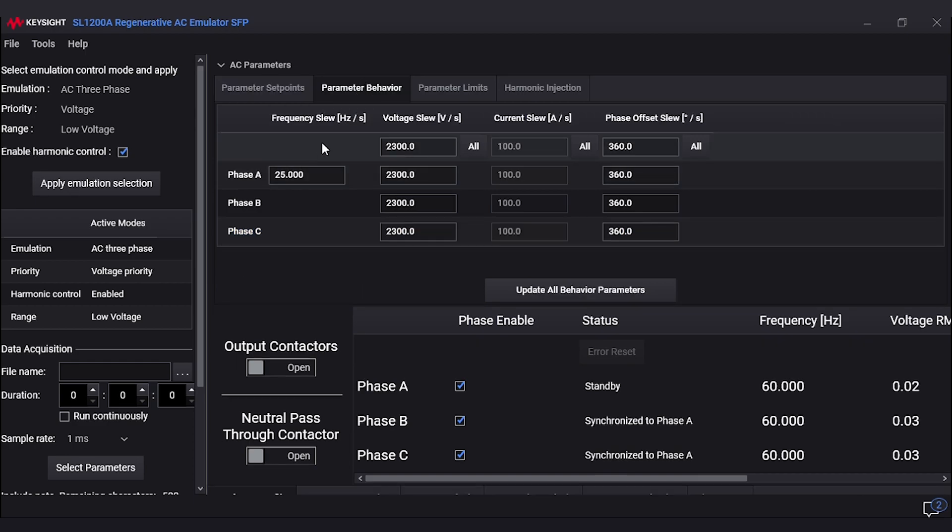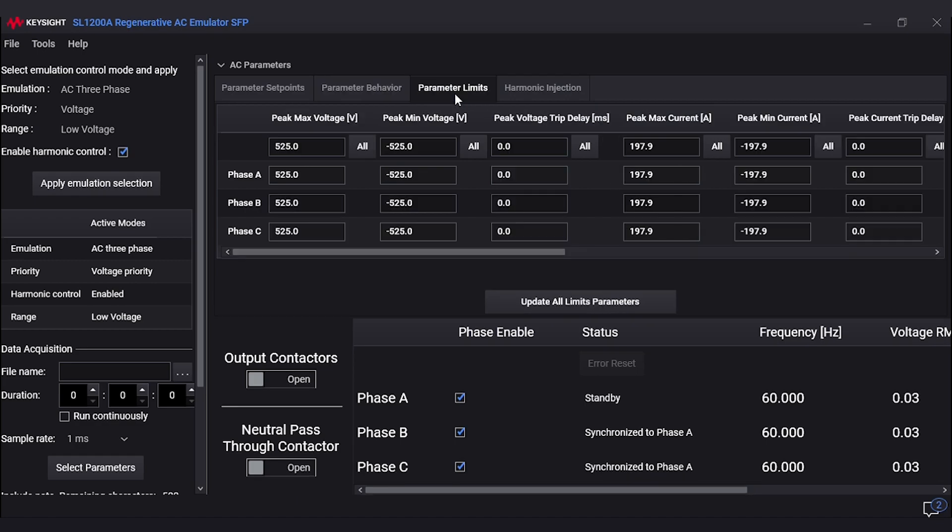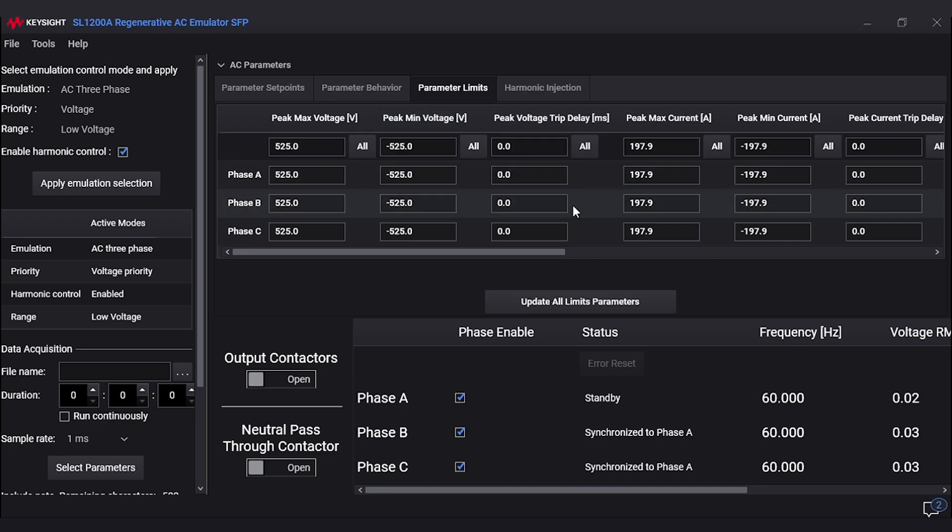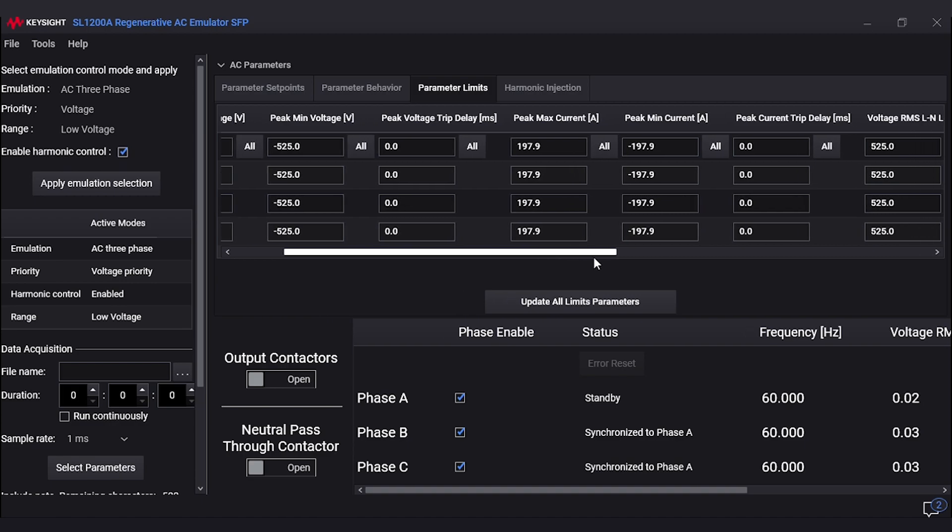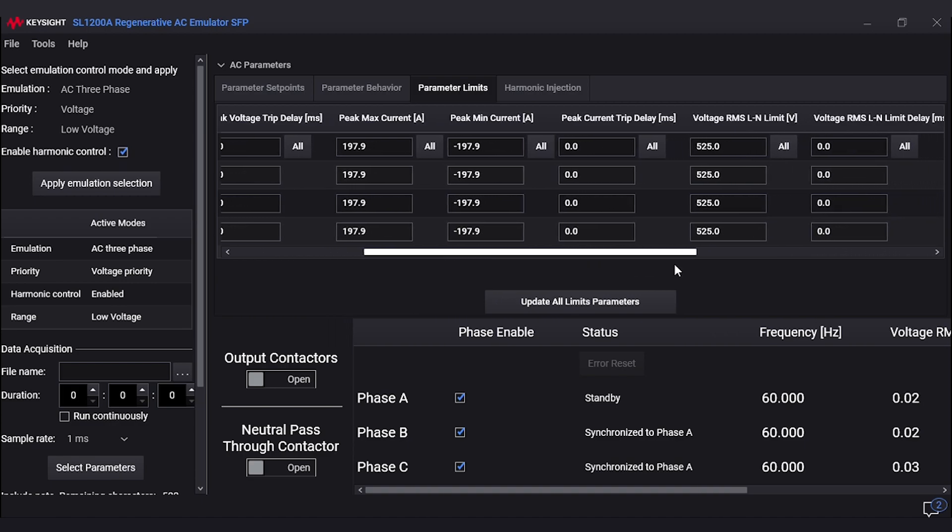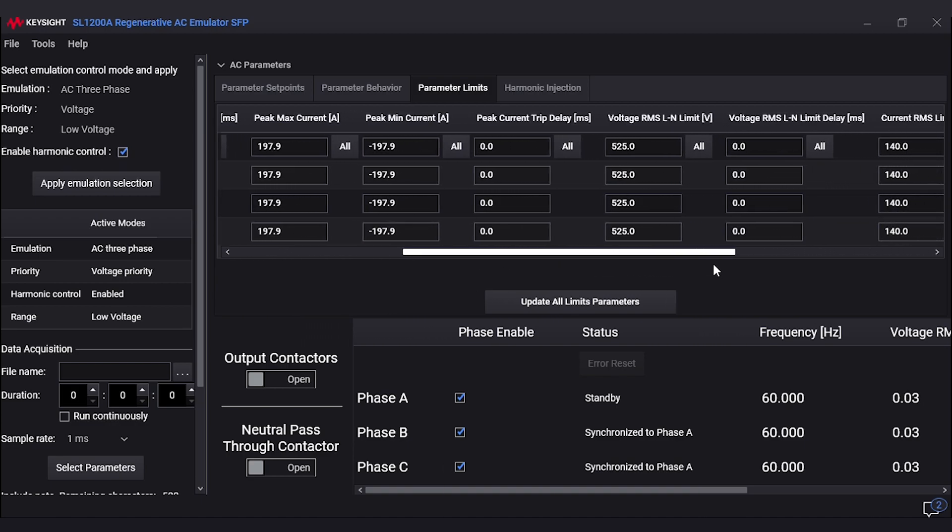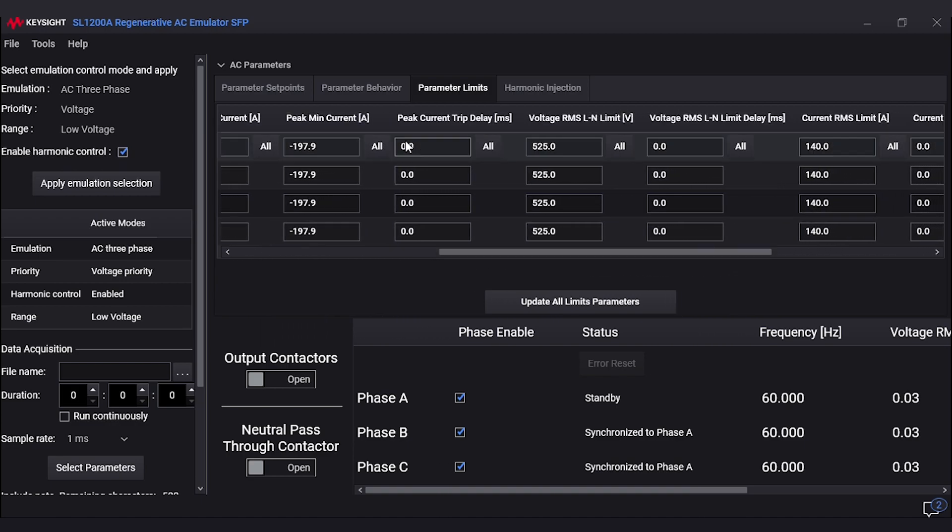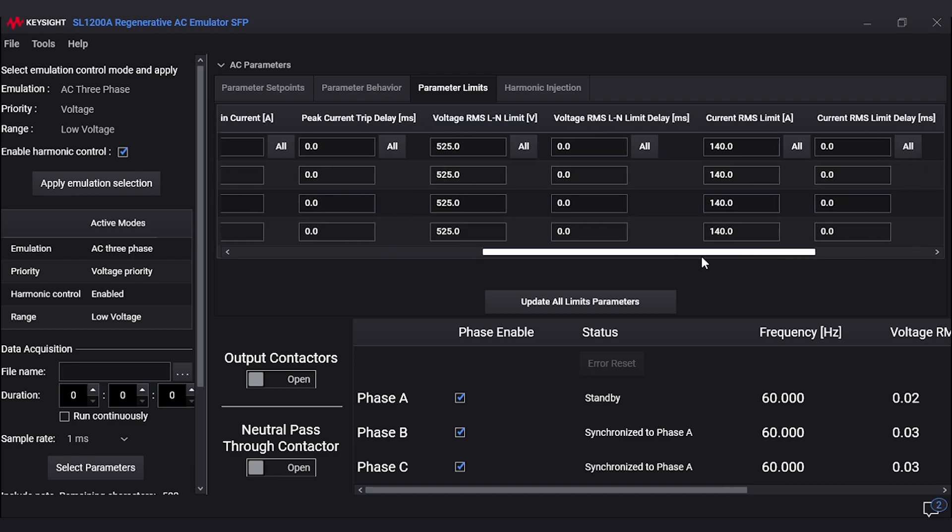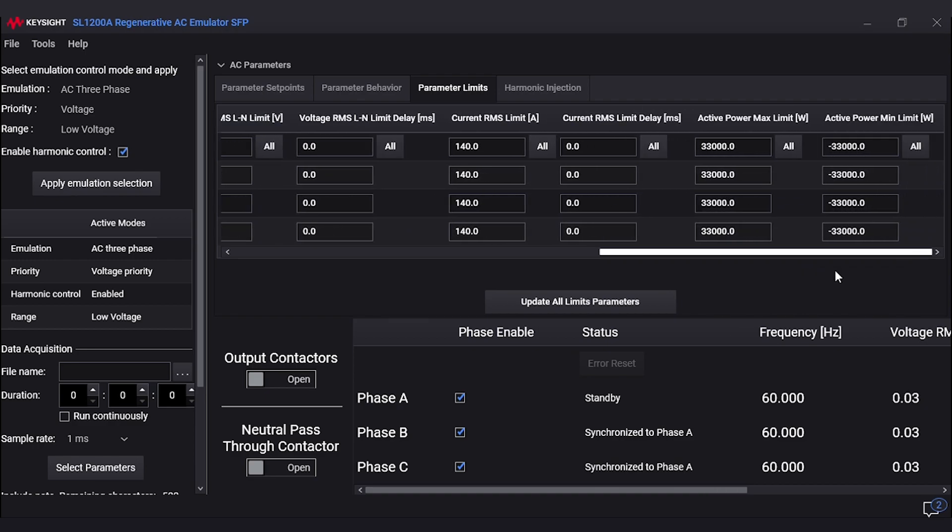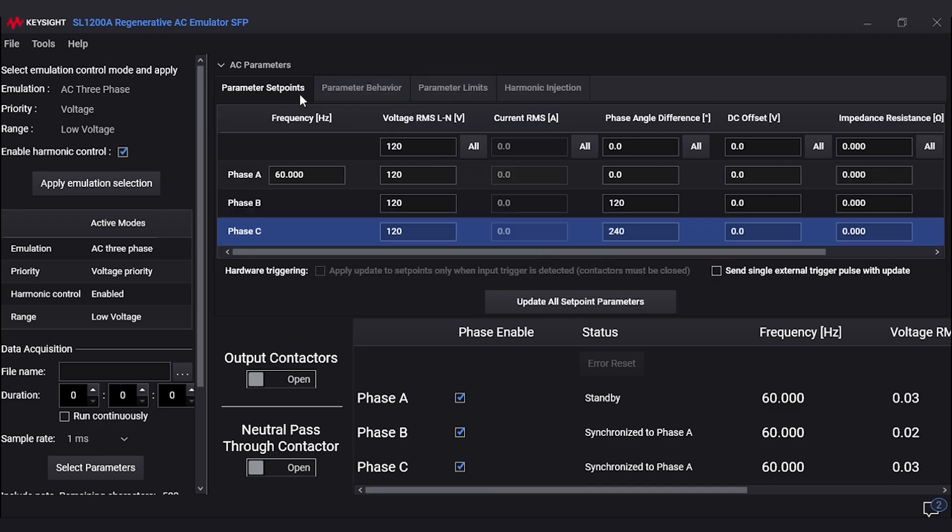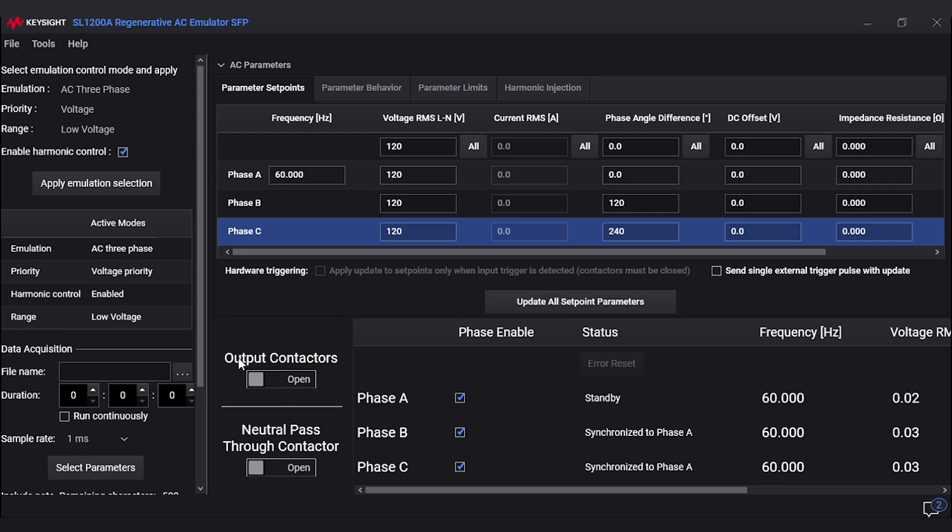Here are the parameter behavior settings that the user may change depending on the test they are doing. The parameter limits section contains the safety limits usually set for the protection of the load. Now we will show all the settings you can change. After adding in potential parameters, we will push 'update all set point parameters' to apply the desired settings.